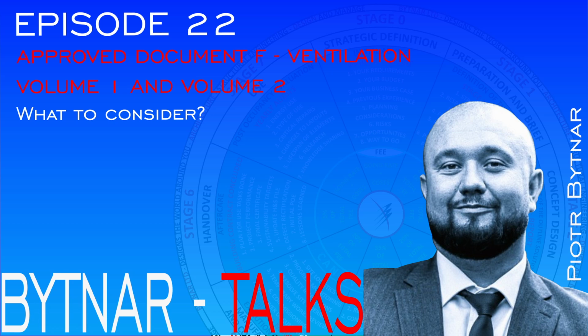Purge ventilation is required for all habitable rooms, allowing 4 air changes per hour, but may need to be greater. The window or door opening needs to be at least 1/20th of the floor area if openable to 30 degrees or more, and below that range of the opening it needs to be at least 1/10 of the floor area. Naturally, a mechanical option is always on hand if we need it.